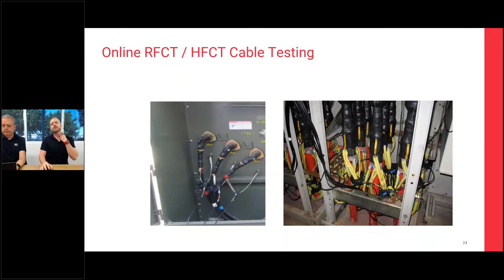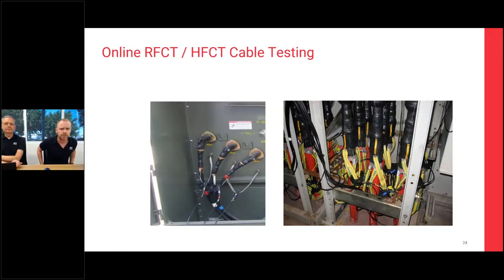In real-world examples of hooking on RFCTs: on the left-hand side we've got a red, white, blue cable terminating onto a piece of switchgear with three RFCTs hooked easily onto the earth screens — a perfect setup for capturing cable PD signals. On the right-hand side it looks busier but is doing the exact same thing, putting RFCTs around the screens coming off each cable core.